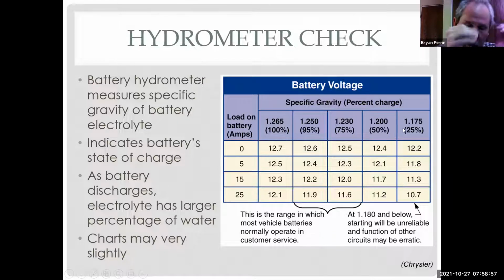So I can use my voltmeter along with the knowledge we've learned from hydrometer testing, knowing that a certain hydrometer reading corresponds to a certain voltage at the battery. If I only get 12.2 volts, my battery doesn't have a full charge — it needs to be charged, or something's going on. If it keeps coming back to 12.2 volts on its own, just sitting on the shelf disconnected, that tells me I've got a weak battery, one that's worn out or on its way out. So I can use this open circuit voltage with a voltmeter to approximate the battery's state of charge.